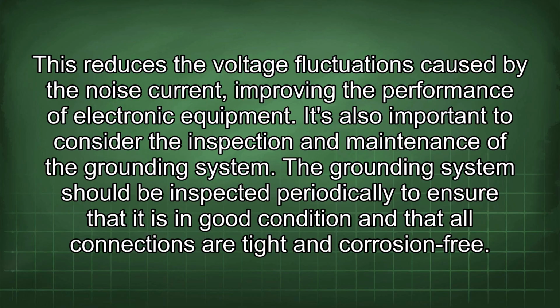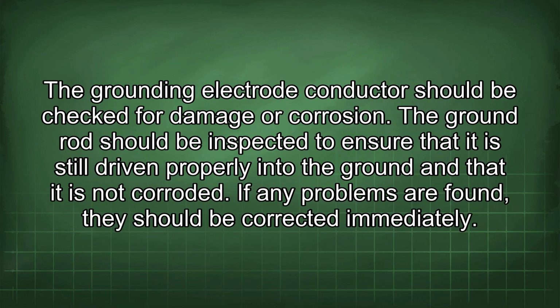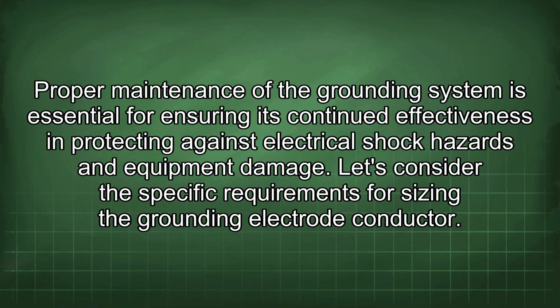It's also important to consider the inspection and maintenance of the grounding system. The grounding system should be inspected periodically to ensure that it is in good condition and that all connections are tight and corrosion-free. The grounding electrode conductor should be checked for damage or corrosion. The ground rod should be inspected to ensure that it is still driven properly into the ground and that it is not corroded. If any problems are found, they should be corrected immediately.